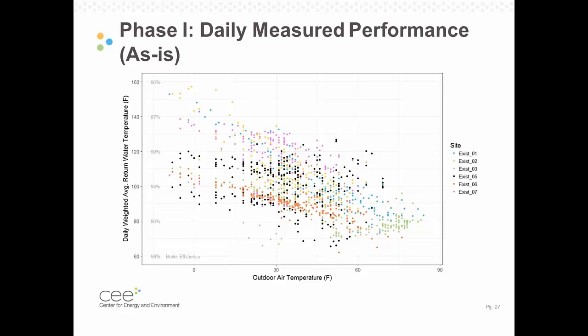And then as it gets warmer out, you can see that reset curve driving those temperatures down to when you're out by 60 degrees. For the most part, those temperatures are below 100 degrees or so. You can see here that in about 3 of the sites, at the very cold temperatures, we did need to increase the capacity outside of that condensing range. However, the amount of data there is small enough that those impacts from those handful of non-condensing days were not high enough to bring the total system heating efficiency below 90%.